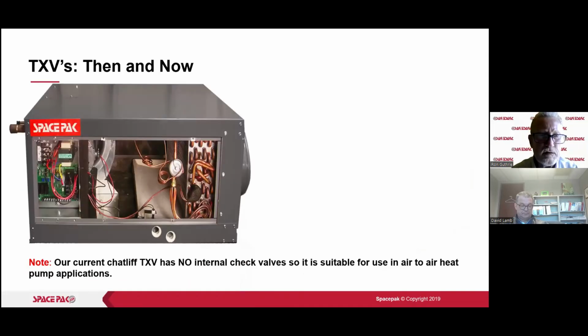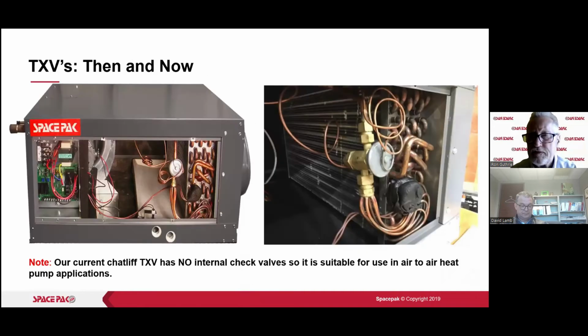All right, TXVs. This probably shows some old stuff here, but just to let you know, we have a Chatleff fitting, so it's a mechanical fitting. If you do have to change the expansion valve, it does come installed. This is a J series, maybe even older, and I can tell that by the right picture. The insulation right there on the front of it is actually the freezestat on this unit. Now we do that with the board. We used to have a separate freezestat mounted right on the coil.